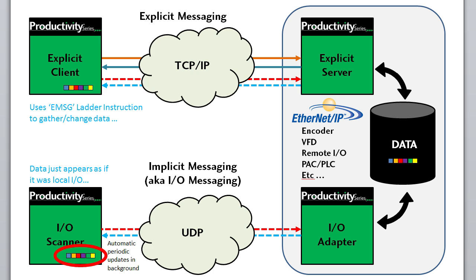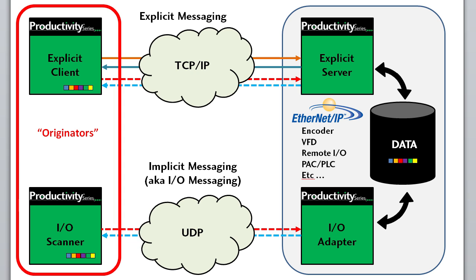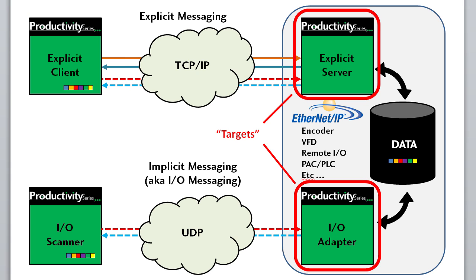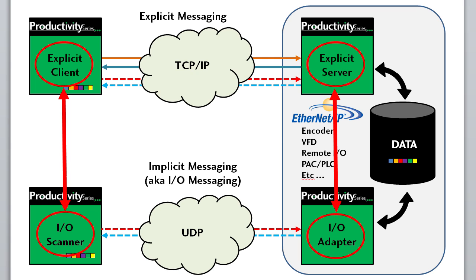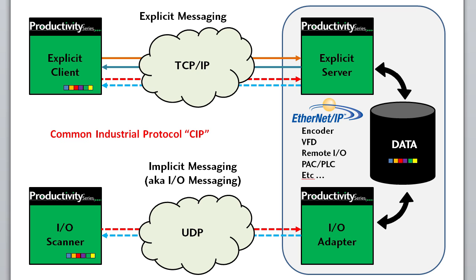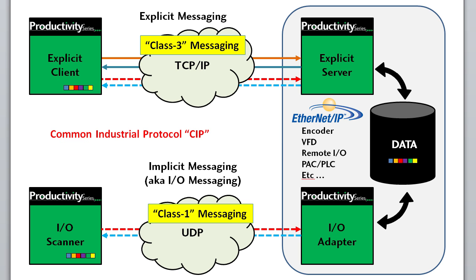A couple of side notes. These are generically called originators because they originate the transfers, and these are generically referred to as targets. Sometimes you'll see folks use these terms interchangeably, so just be aware of that. The Common Industrial Protocol, or CIP, refers to implicit messaging as class 1 messaging and explicit messaging as class 3 messaging, so you may hear those terms used sometimes too.